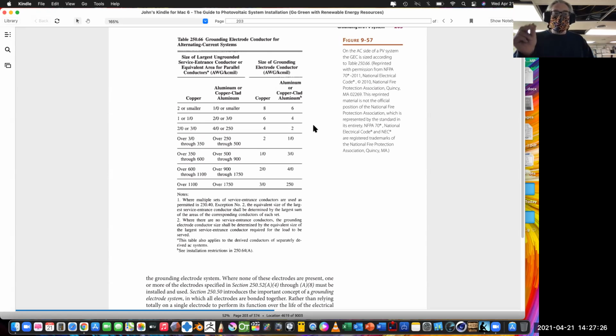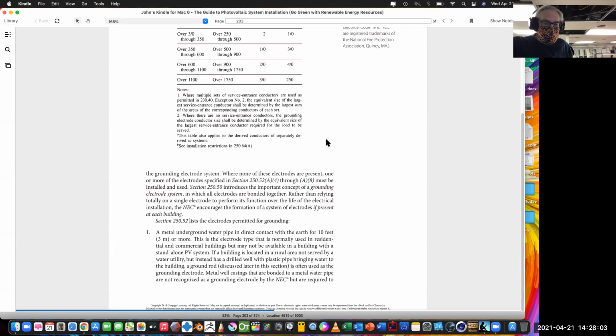You're asking for it. It's better to just oversize these things that are really tight on the numbers. Number 6 is tight, I'll tell you that. I would have liked number 4 better, but it raised the cost a bit more because we're going 200 feet with parallel conductors. It just raised the cost, so we had to make an executive decision and go, it'll be fine. And it is — it's fine, but you've got to know it'll be fine. So in this case, you want to make sure you size the system properly, and if you don't know what it is, oversize.